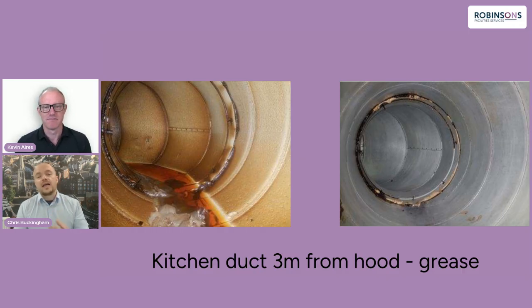Should any sort of high volume of heat or flame connect to that, there is a very good chance that itself would create a fire. And in this unit specifically, and in general, this ductwork's not fire rated. So should the fire start within that ventilation, it will burn out and it will spread. And that's why it's so important, especially with pooling grease like that. That's the worst kind you could get, really. Well, and of course, as soon as it leaks out, it's going to be burning oil that's coming out, right? Yeah, exactly, grease, right. I mean, there's a whole list of problems should you get a fire within that, and there's just no need for it. There's no need for it.